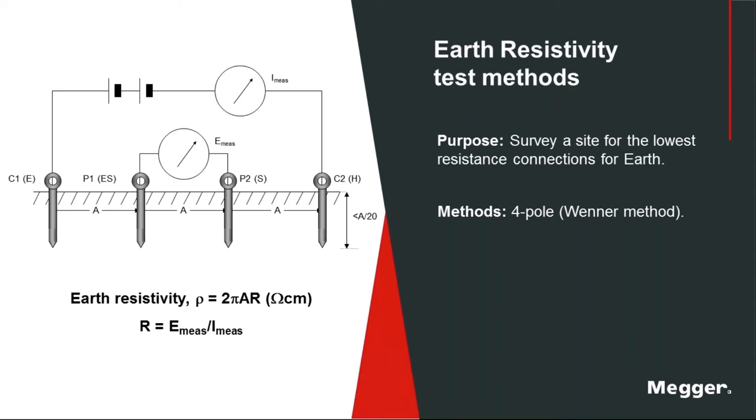Resistivity is a volumetric measurement. Your soil is three-dimensional. So you need to correct for that. That's where you see that little formula down there: two pi ar. Two times pi, then a would be your spacing, and r would be your resistance off of your meter. That would give you your soil resistivity in Ohm centimeters.